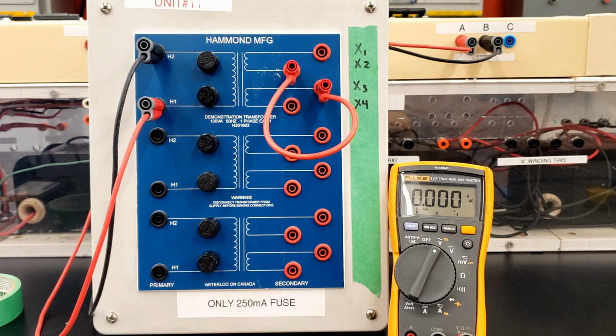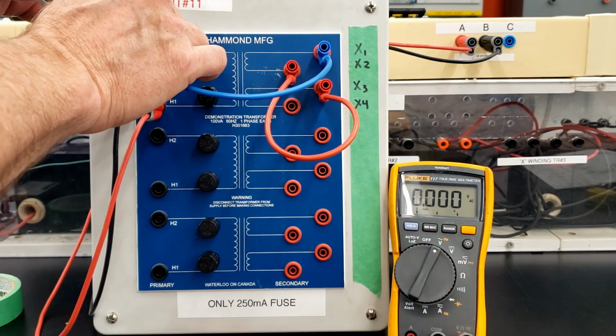Okay, this is a little bit unusual. I'm now going to connect up the primary to the secondary. It's unusual because you don't normally connect the primary to the secondary, but we're going to create something like an autotransformer, where the primary windings and secondary windings are in series. So I'm going to put X1 to H2, or what I think is X1 to H2.